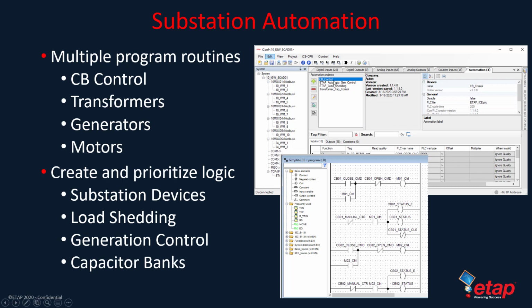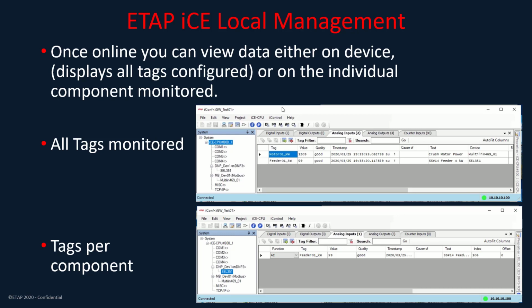The device can handle multiple programs on the configuration. In this case, we're looking into a configuration that is using protected device control, generation control, and also we're using it for other ETAP applications. Once the device is online, you can view the data, and also you can display it when you want to monitor the device locally for debugging purposes. You can view the state of each one of the measurements that are going along your device, just to determine, in the case that you need to perform any type of maintenance on the device, the information about the measurements that the device is collecting, as well as the device.